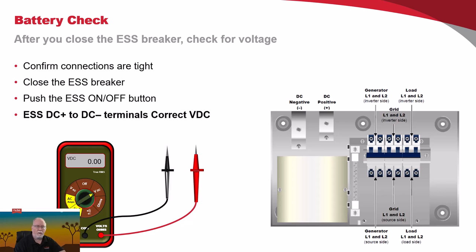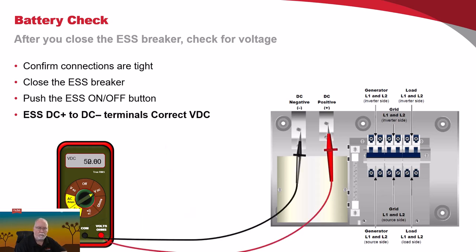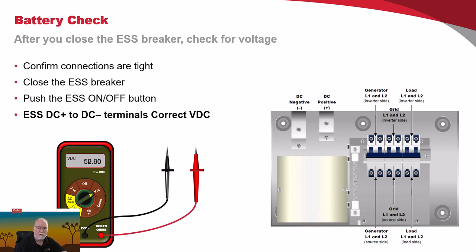So the next thing is a battery check. Confirm your connections are tight. Close the ESS breaker. Push the button momentarily in the ESS, and then check for connection at the base of the inverter. You should see between 50 and 52 volts. Everything looks good. Go ahead and close your breakers for grid input and load output generator if you need to, and you're off and running.